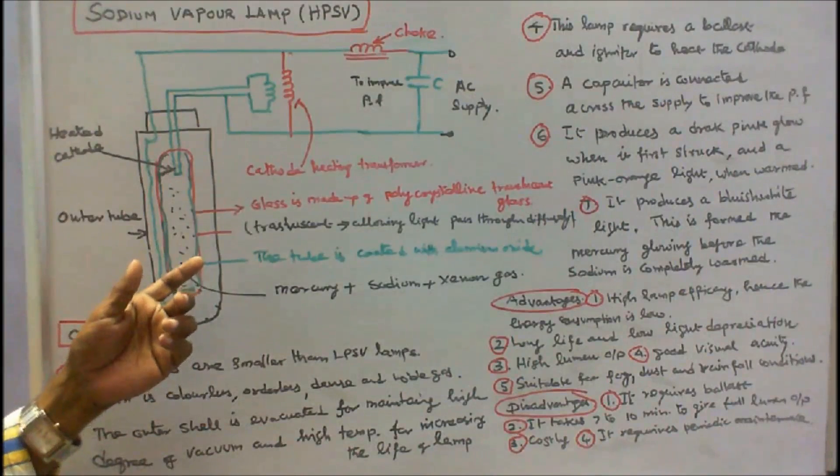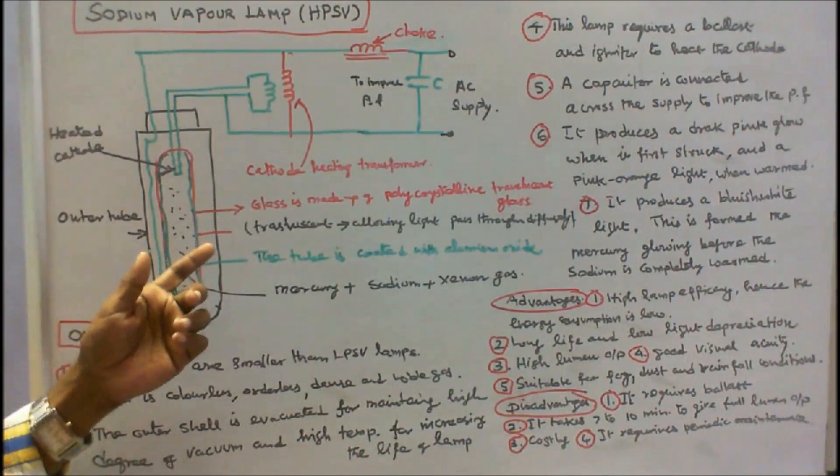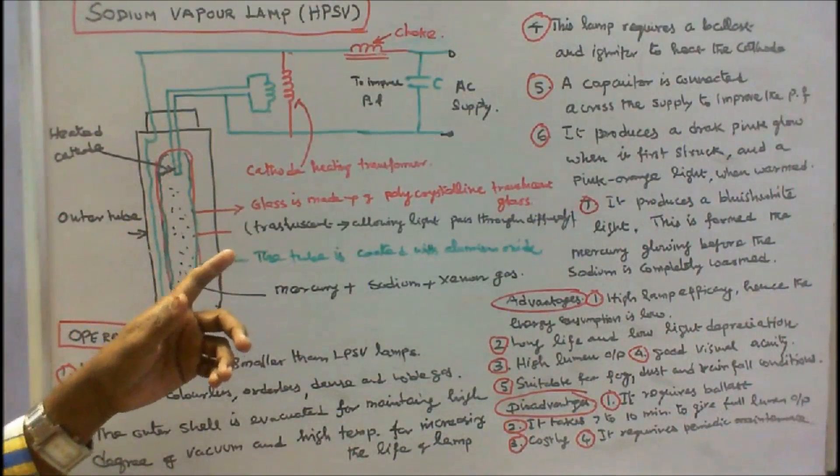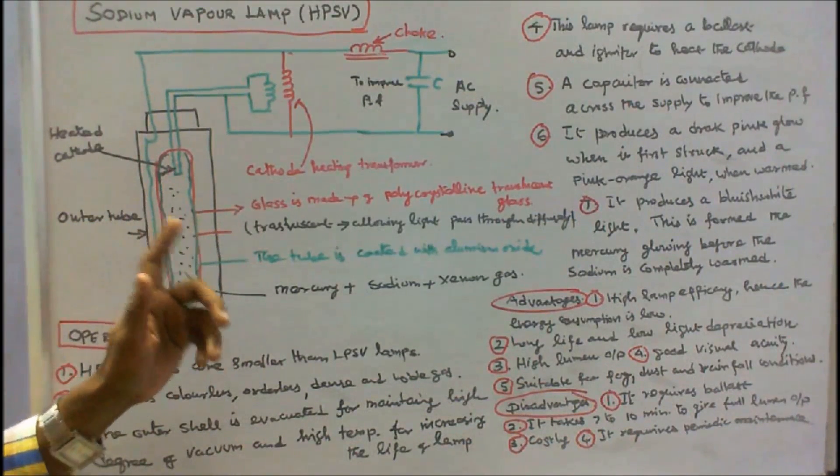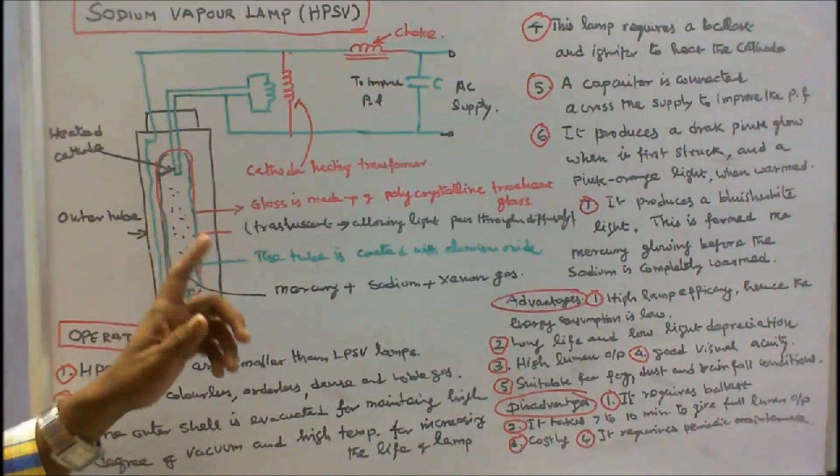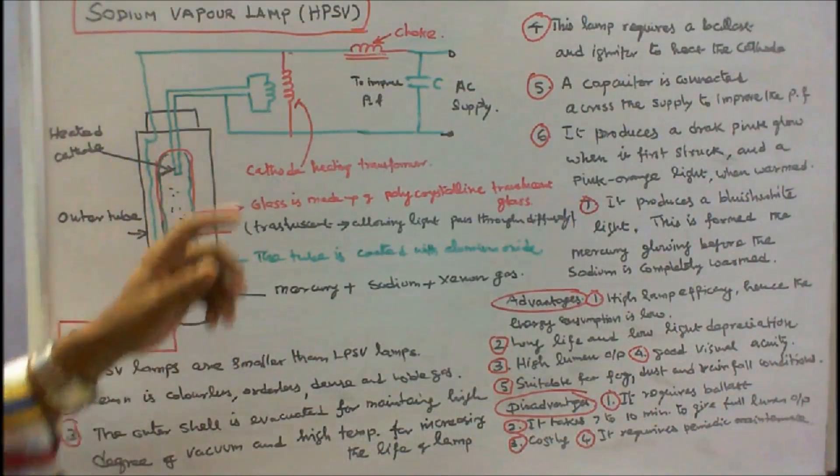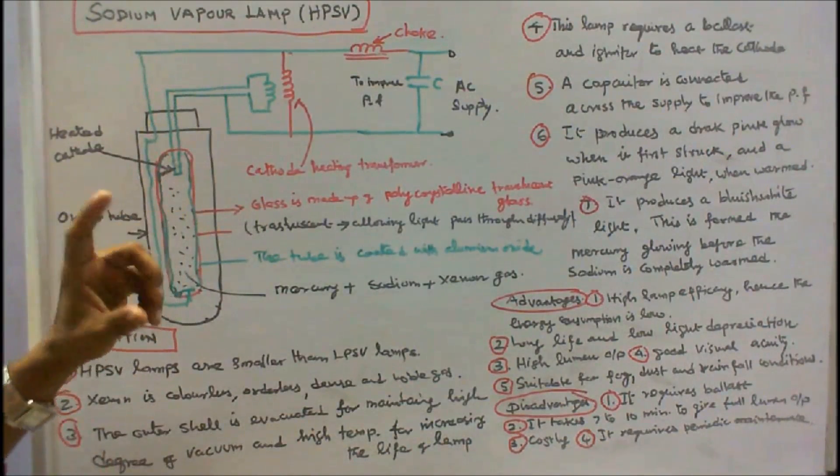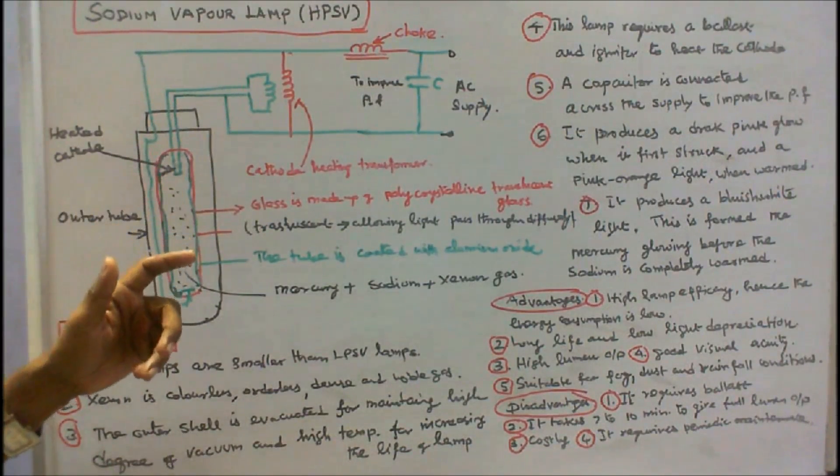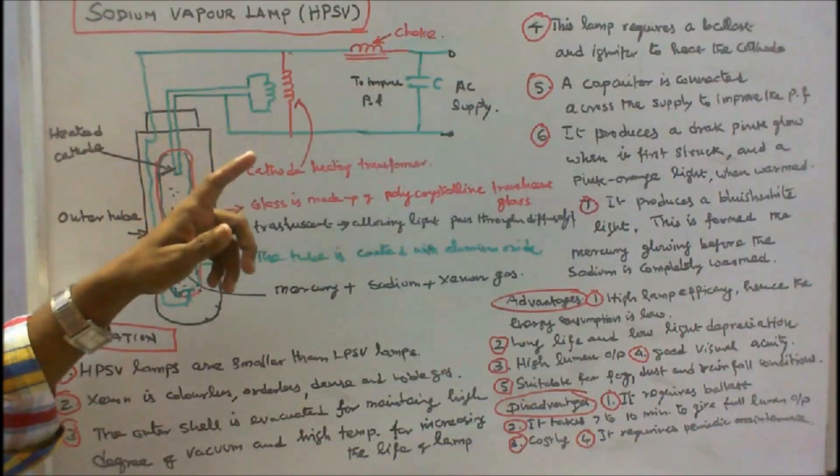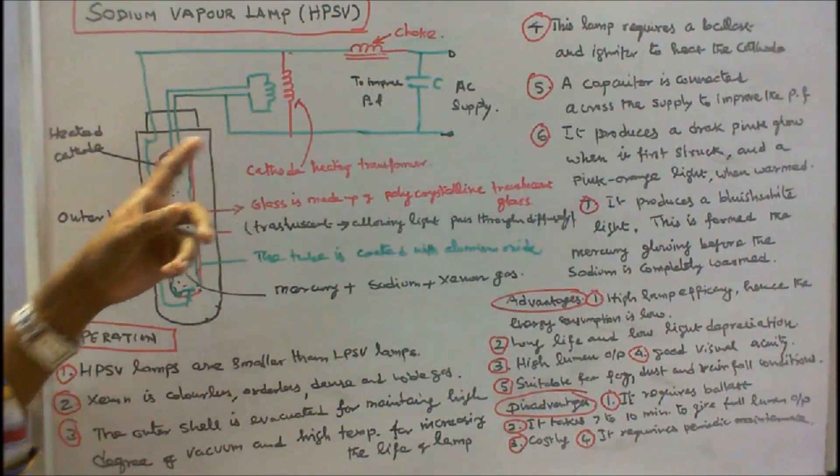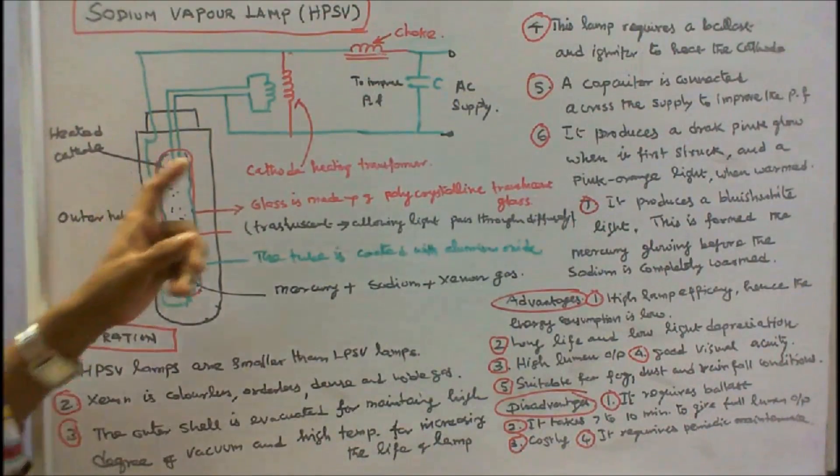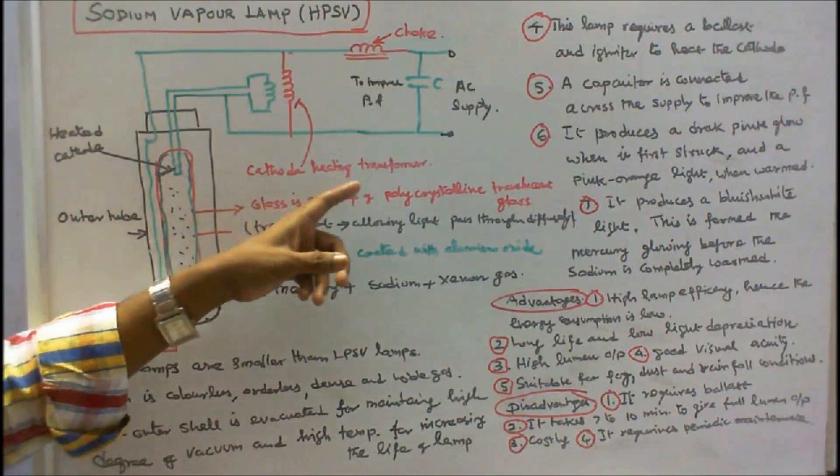This is a figure of a high pressure sodium vapor lamp. Sodium vapor lamps are suitable only for AC supply, hence we need a ballast. Here a choke is connected. It requires high voltage at the time of starting. Hence we go for a high reactance transformer or an auto transformer to heat the cathode. Hence it is called as cathode heating transformer.